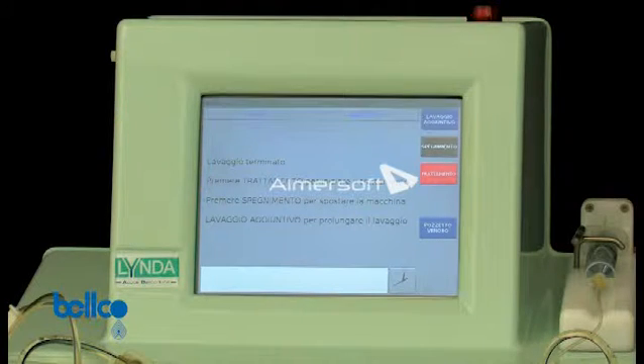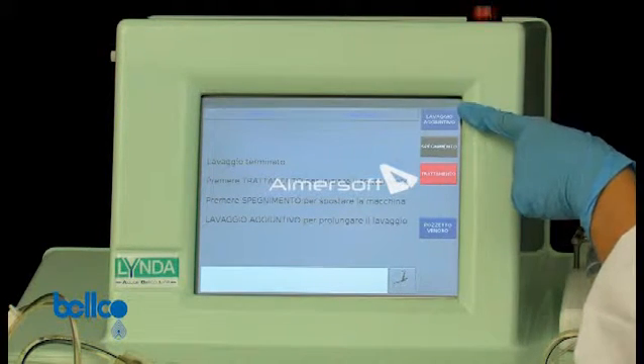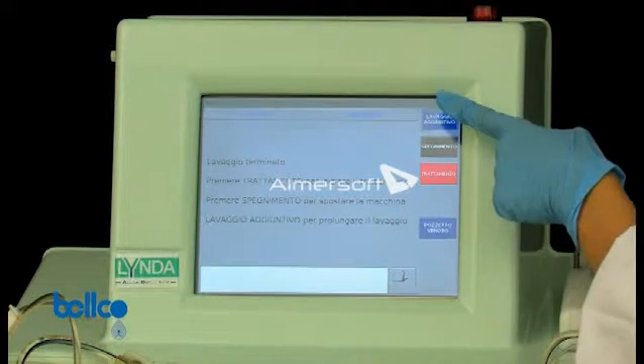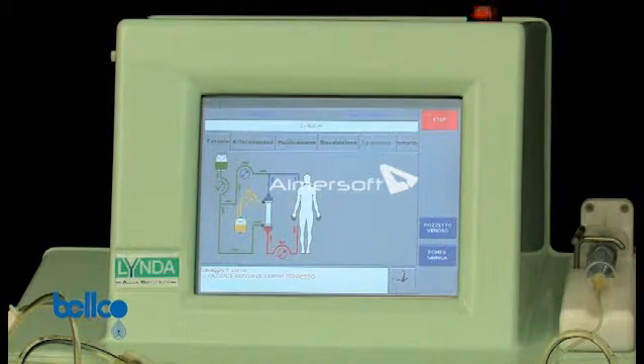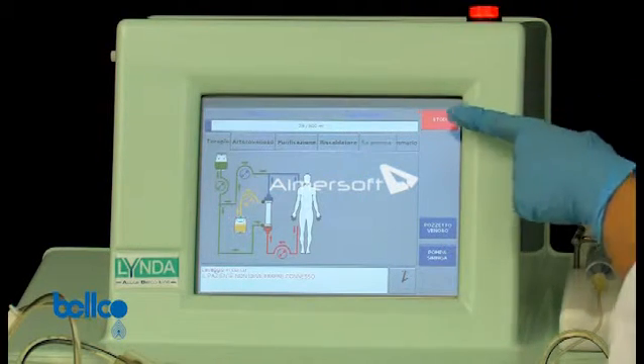You can start performing additional rinsing by tapping the additional rinsing button. The machine will restart with a complete rinsing of 4 liters. This additional priming can be interrupted at any time simply by tapping the flashing stop button.